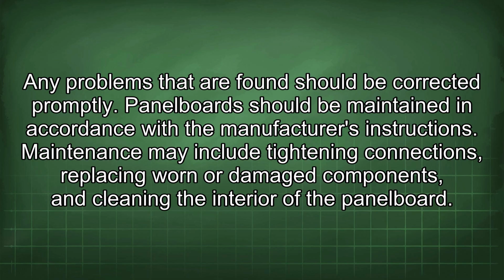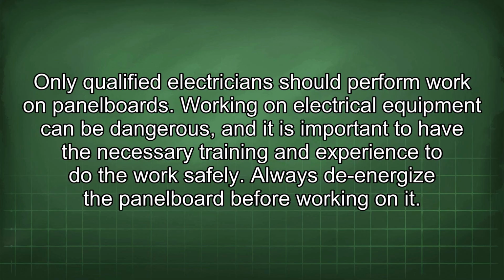Panelboards should be maintained in accordance with the manufacturer's instructions. Maintenance may include tightening connections, replacing worn or damaged components, and cleaning the interior of the panelboard. Only qualified electricians should perform work on panelboards. Working on electrical equipment can be dangerous, and it is important to have the necessary training and experience to do the work safely. Always de-energize the panelboard before working on it.